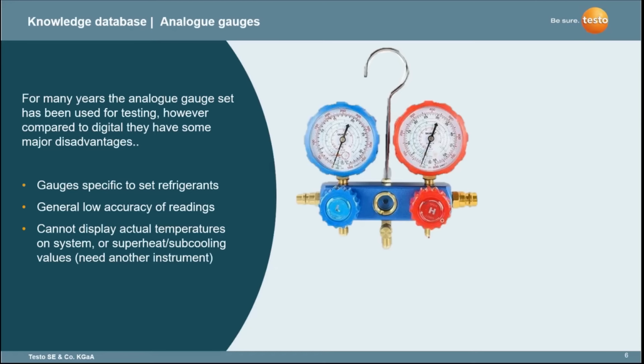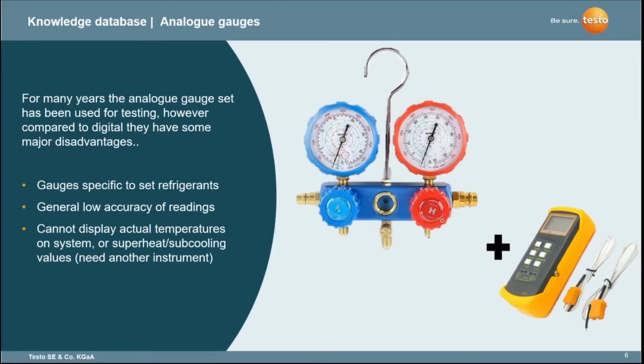For many, many years, the analog gauge set has really been the go-to for refrigeration, air conditioning and heat pump engineers. But compared to digital, they really do have some major disadvantages. Typically, they're of fairly low accuracy from a pressure and temperature point of view. They're often specific to a set of refrigerants, so the temperature scaling within the dial will be specific to one or two refrigerants, and they can't display any actual temperatures. For that, you're going to need another device such as a differential thermometer. And if you're working with various refrigerants, as refrigerants change, you're going to need access to the pressure and temperature lookup tables as well. It's this combination of having to do quite a lot of manual reading of dials, ancillary instruments and charts where the move to digital really makes things so much simpler, because a lot of this is shown in a completely different, much more easily accessible way for the engineer.